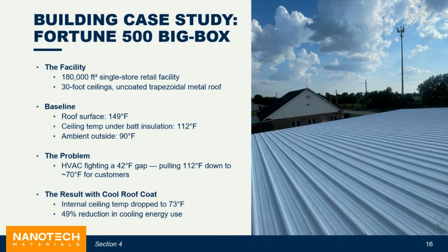What you're seeing here is a 180,000 square foot retail facility, a standard retail store that you'd walk in, with 30-foot ceilings and large open spaces. We coated an uncoated metal roof, and at the baseline, the roof surface hit 149 degrees when it was only 90 degrees outside. So the ambient temperature was 90 degrees. But this is actually their data. What they did was go inside the facility, take a thermal gun and read the temperatures right underneath the ceiling tiles, right under the batt insulation, and it was reading 112 degrees.